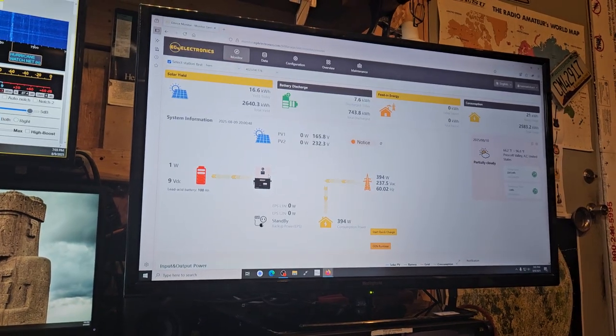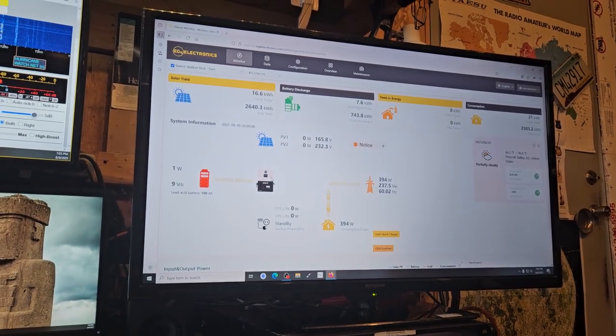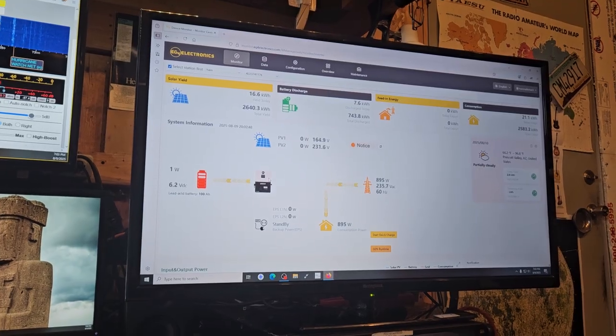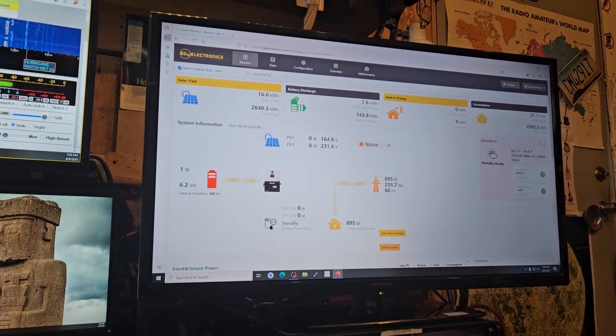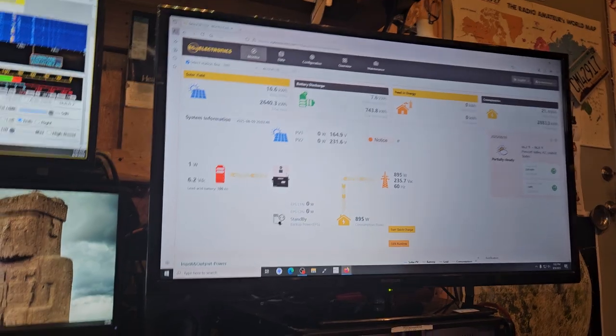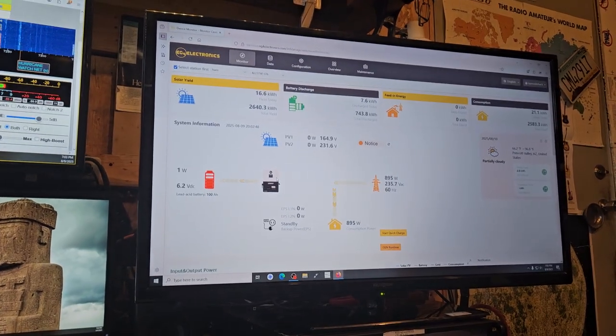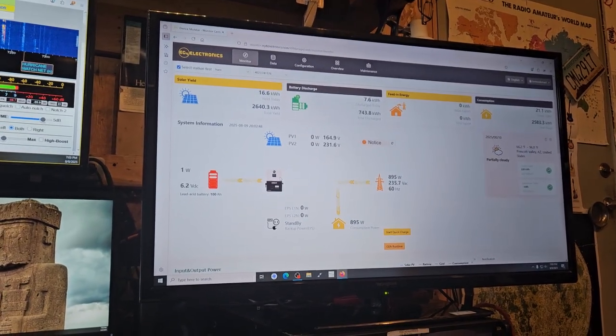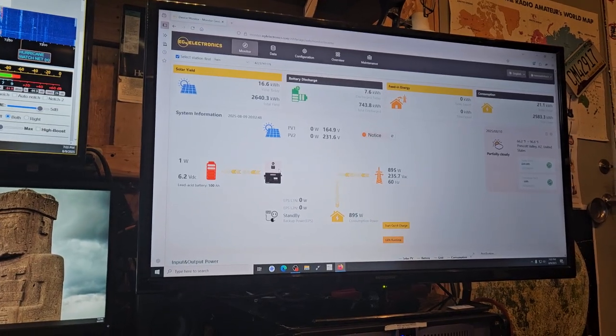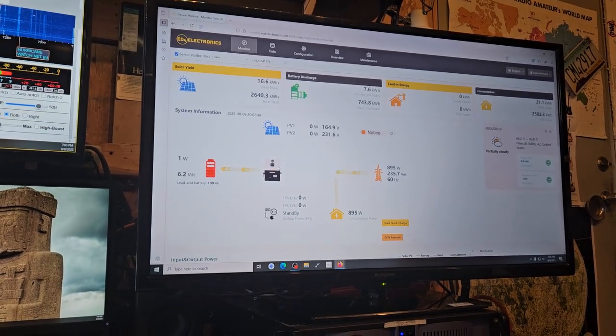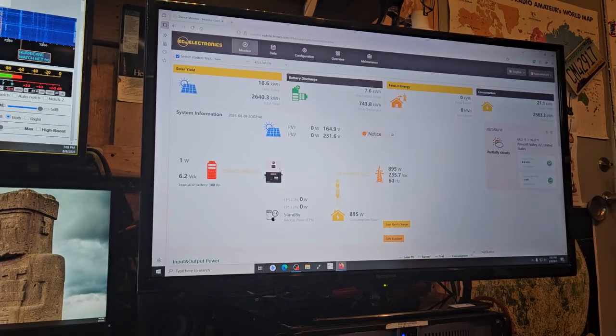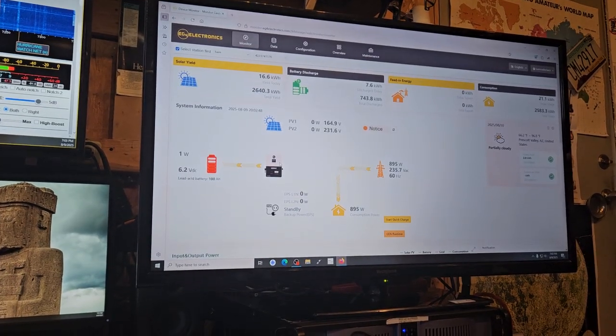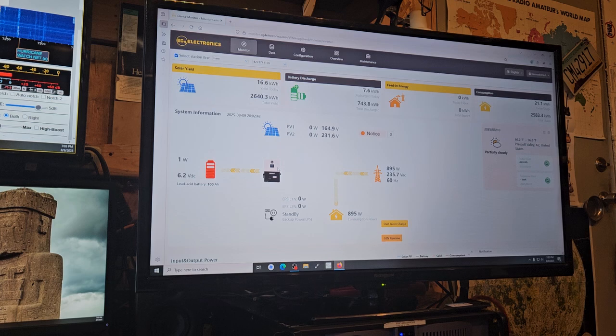So it's a problem that happens when you use 4 12-volt batteries. It's just going to happen. You can get battery balancer type things, but the problem with this inverter is you can't set your cutoff voltage low enough to use all your batteries up, because the BMS is going to pop. This is a problem you wouldn't actually have with lead acid batteries, so there's one advantage there.